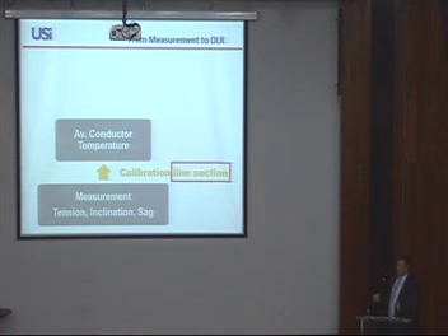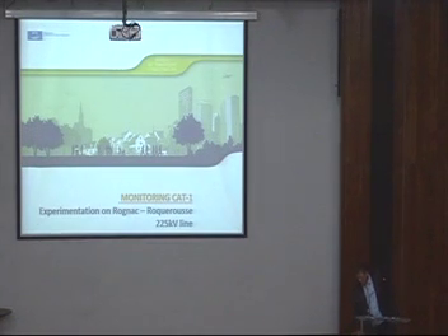So from the tension, from the temperatures we are measuring with a special sensor, or from the inclination and weather data, we have a very, let's say, excellent methodology to determine the real condition of a transmission line, the relationship. And it has been tested and verified by a number of customers that what we are doing here is very accurate. One of the customers was RTE in France. On their pilot project a number of years ago, they went out and verified what is the real conductor temperature and what is the temperature based on tension measurement.